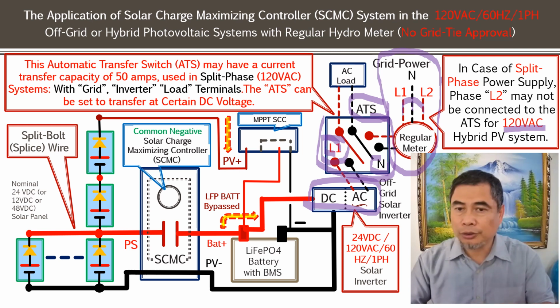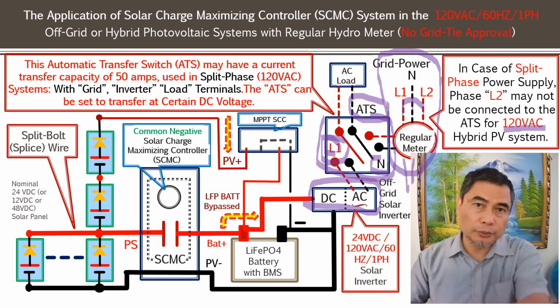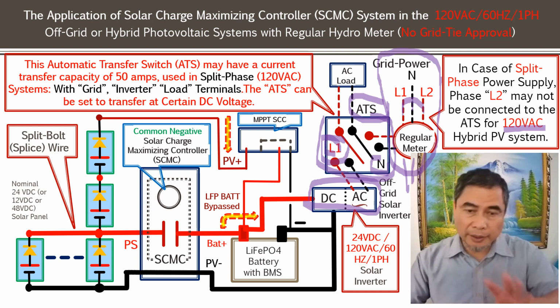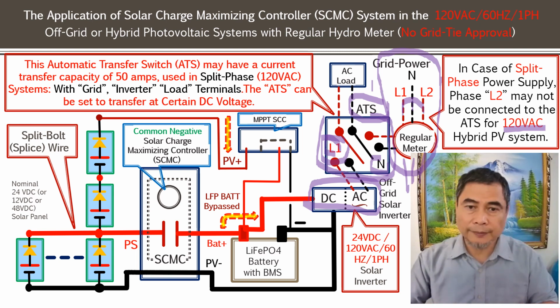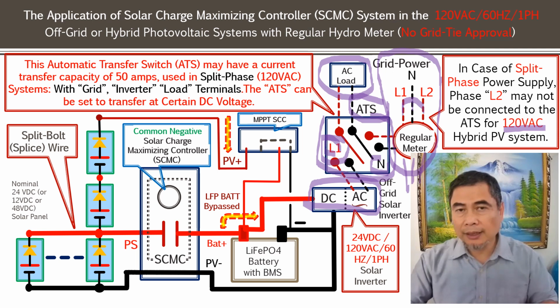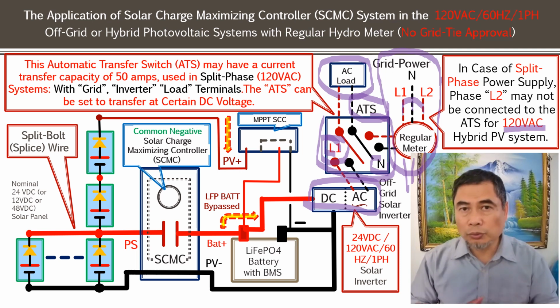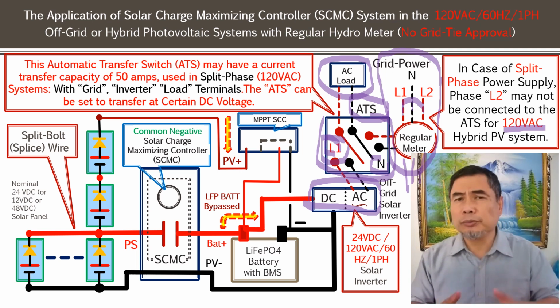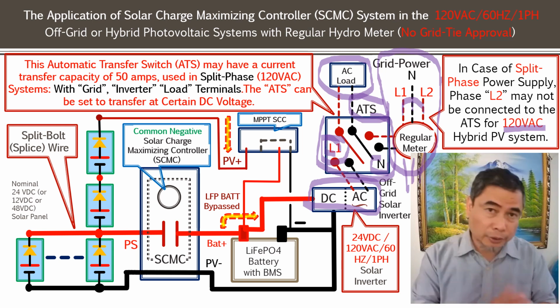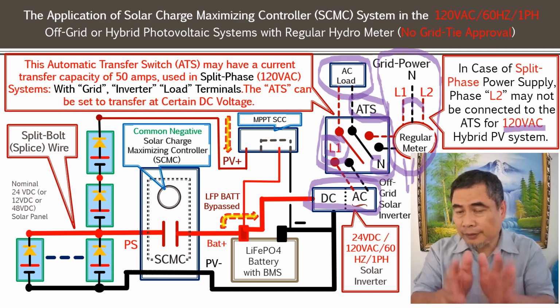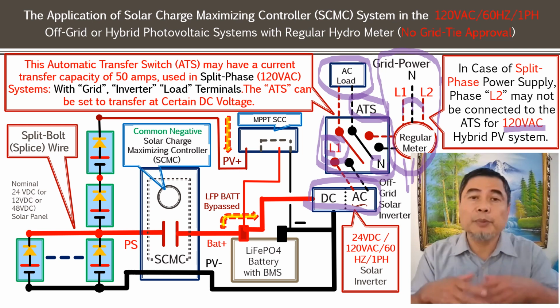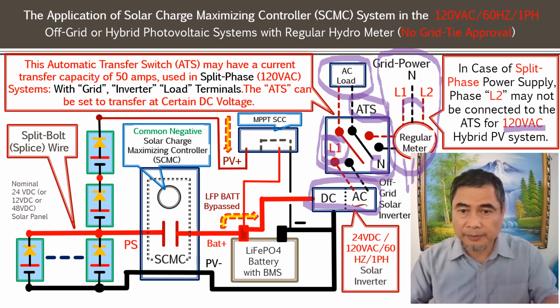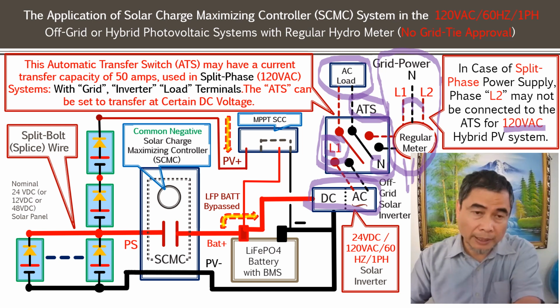L1 connect, L2 is not connected. Probably you can have the load connect to somewhere here for L1, L2, or L2 to neutral. But this portion here, we call them the AC load, mainly consumed during the day, or emergency power supply for the building. This load there can be powered by the PV system without even grid power supply.